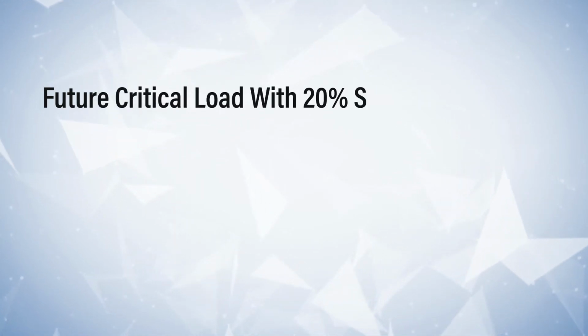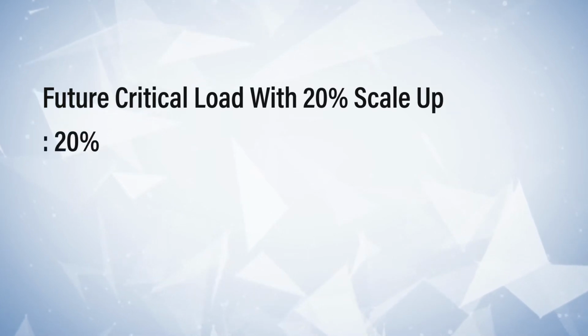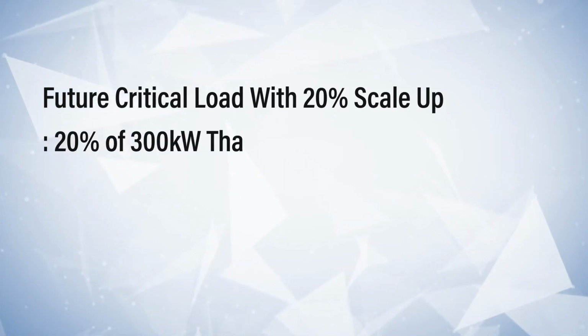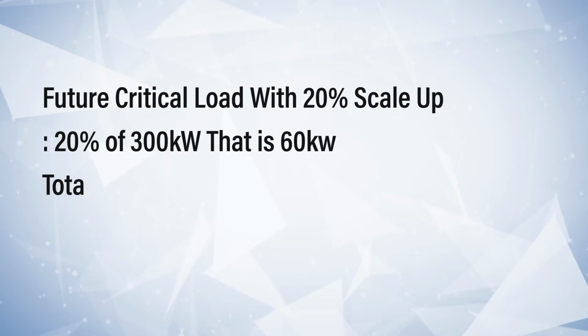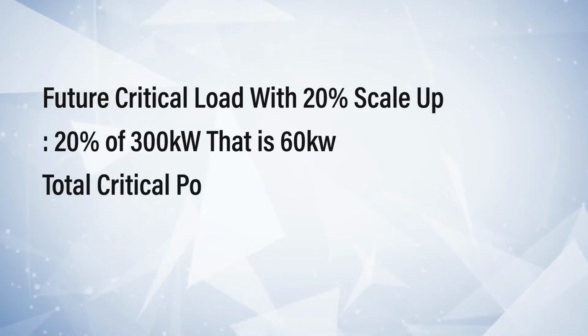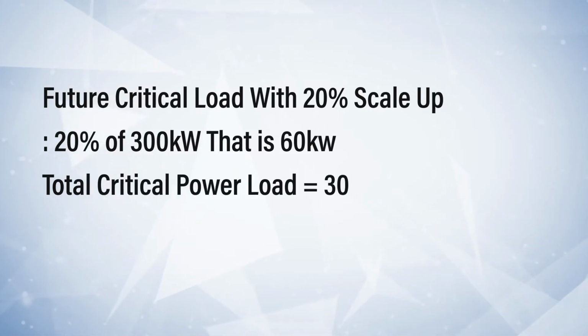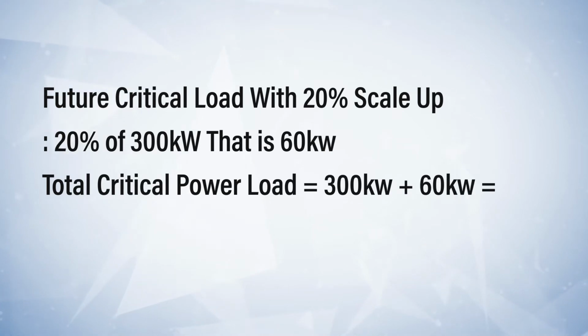For that, let us take our calculation further and first calculate the future critical load power. Let us assume that we will scale our data center by 20% after a few years. So with our calculation of 300 kilowatts critical power, we need additional 20% power down the line, which will be 60 kilowatts. This is 20% of 300 kilowatts. So now the total critical load is 360 kilowatts.